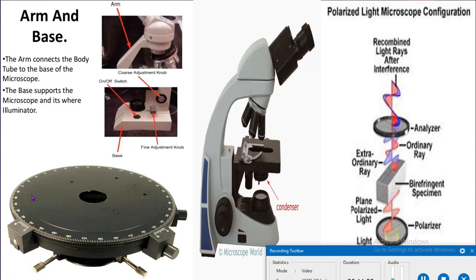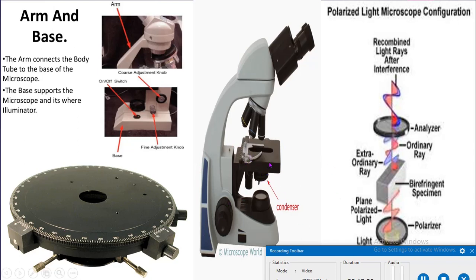The substage apparatus is present beneath the rotating stage and consists of the polarizer, iris diaphragm, and one or two filter holders, which can normally be raised and lowered as a unit. The condenser is located just below the stage and consists of two simple lenses. Its function is to supply a cone of light sufficient to fill the front lens of the objective, giving maximum illumination, and it produces converging light rays when used with high-power objectives.